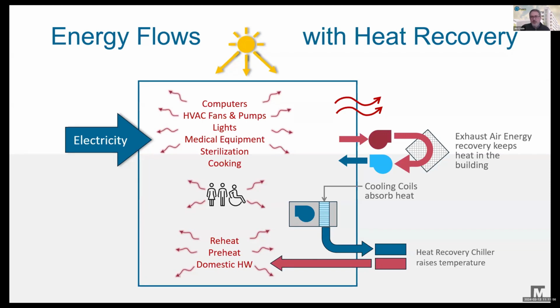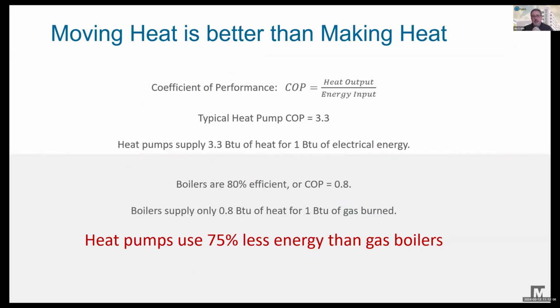So when we talk about a heat recovery chiller, we're talking about moving heat. A heat recovery chiller is a form of heat pump, and the typical COP of a heat pump—basically the ratio of heat we get out to the energy we put in—is about 3.3. So we put in one BTU of electrical energy and get about 3.3 BTUs of heat out. That heat has to come from somewhere; we're not manufacturing heat, but we're moving it much more efficiently than a boiler, which is only about 80% efficient, a COP equivalent to 0.8. So a heat pump uses about 75% less energy than a gas boiler to produce the same amount of heat.